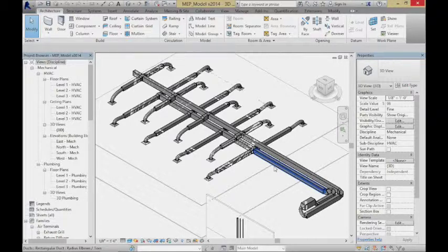As you try to move air, like in most things in engineering, the closer to round you can get, the better in terms of the efficiency of the system. We often find big old squarish ducts like this. We occasionally find really flat, squishy ducts like this. The problem is, as we route ductwork through a building, if the shape isn't right and we're trying to push high volume through that, we get noisy duct systems, and duct systems where there's a lot of static electricity coming through the duct. It's better not to have things that are too squishy. We can push more air through this than that. It's just a more efficient shape.